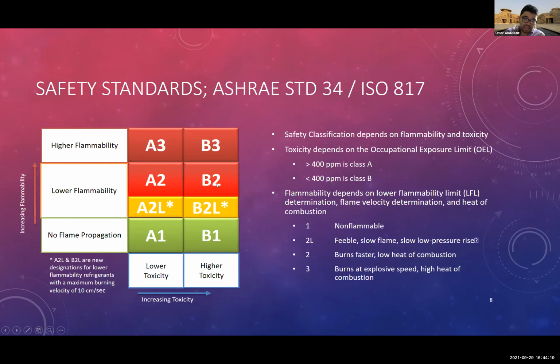A new limit was created recently, called 2L, which is a case where the refrigerant will not sustain fast flame propagation. So we call it feeble, slow flame, and slow, low pressure rise. Then we have A2, where the refrigerant burns faster and there is low heat of combustion, and A3, or 3, that is when it burns at explosive speed and there is high heat of combustion. Again, examples for A1 include normal refrigerants like R134a and R22. A2L includes some of the HFOs like R1234yf. A2 includes, for example, R152a. A3 are mainly hydrocarbons like isobutane, propane, and so on.